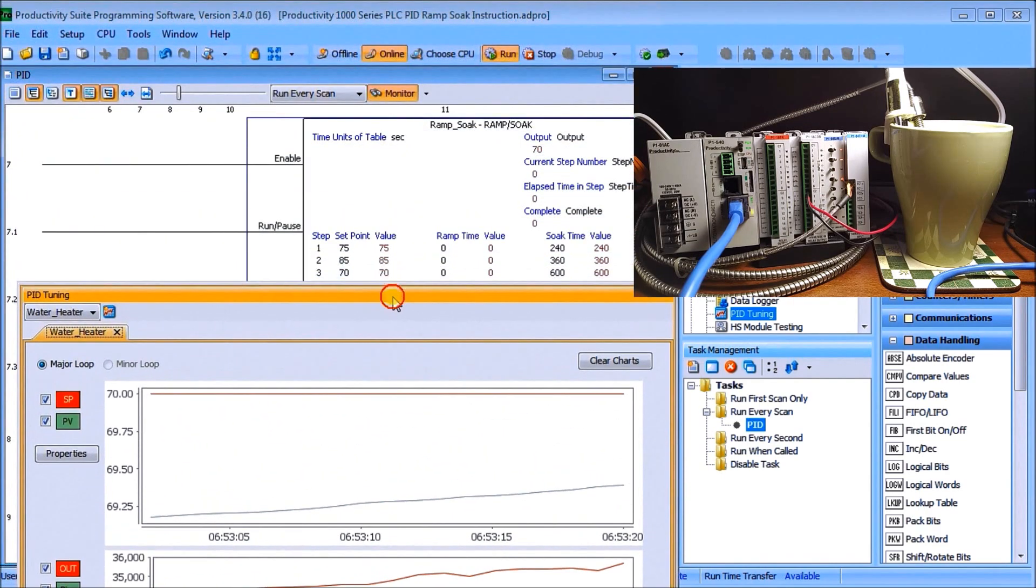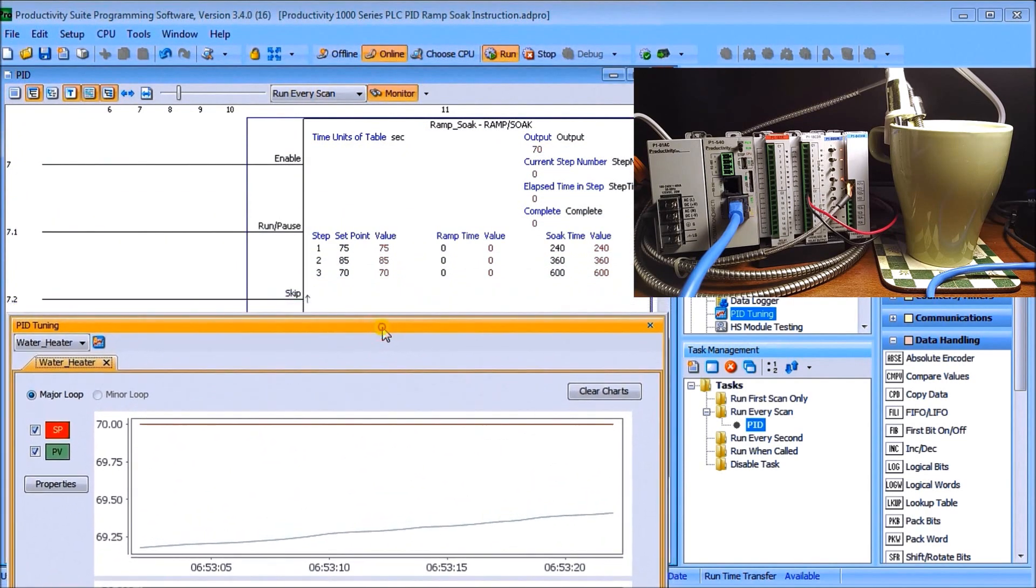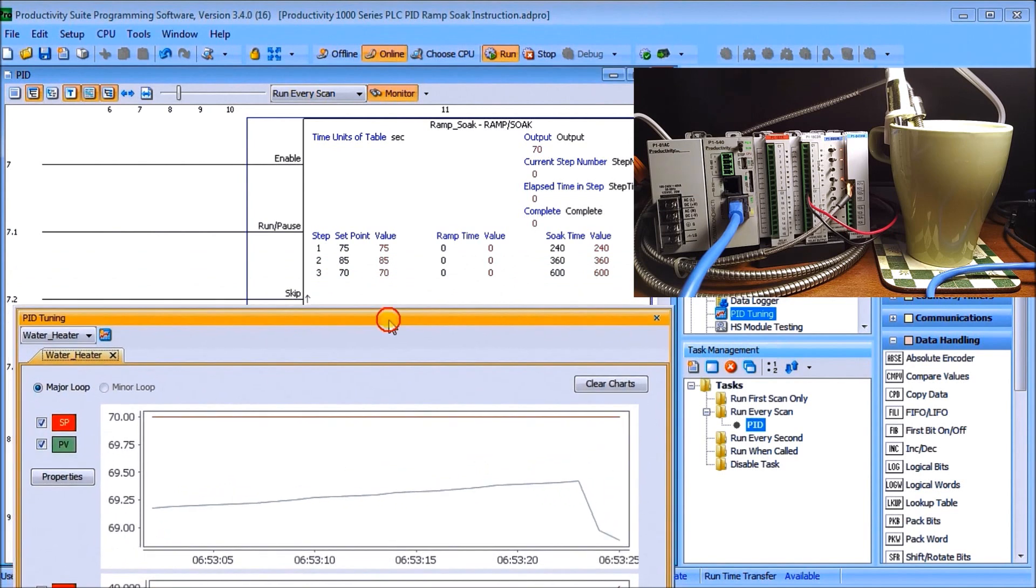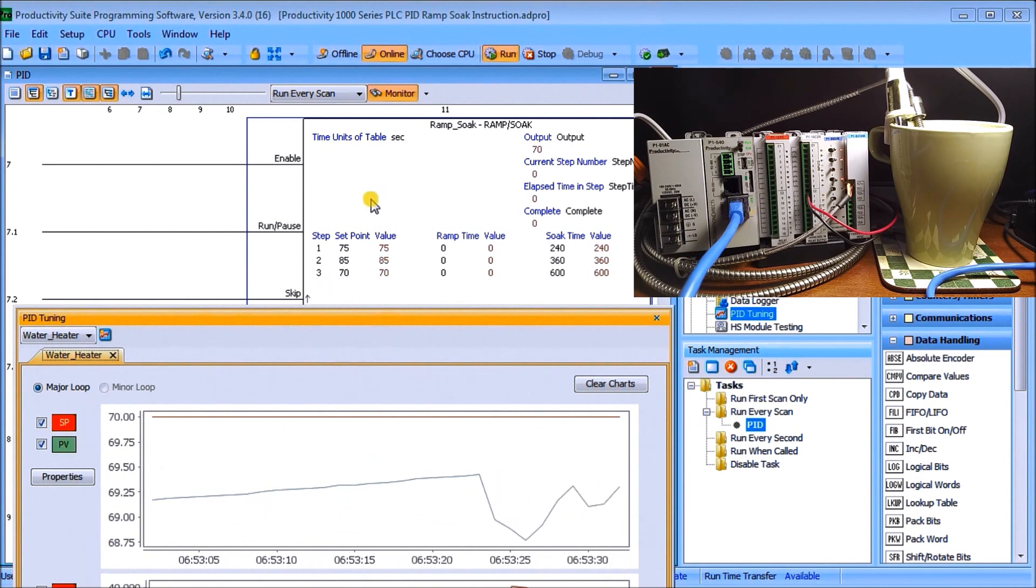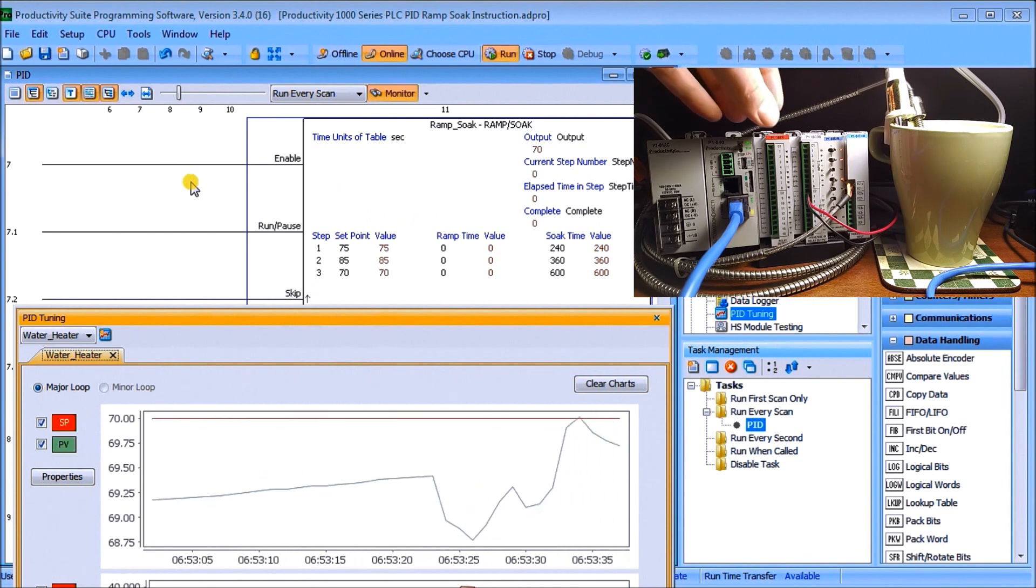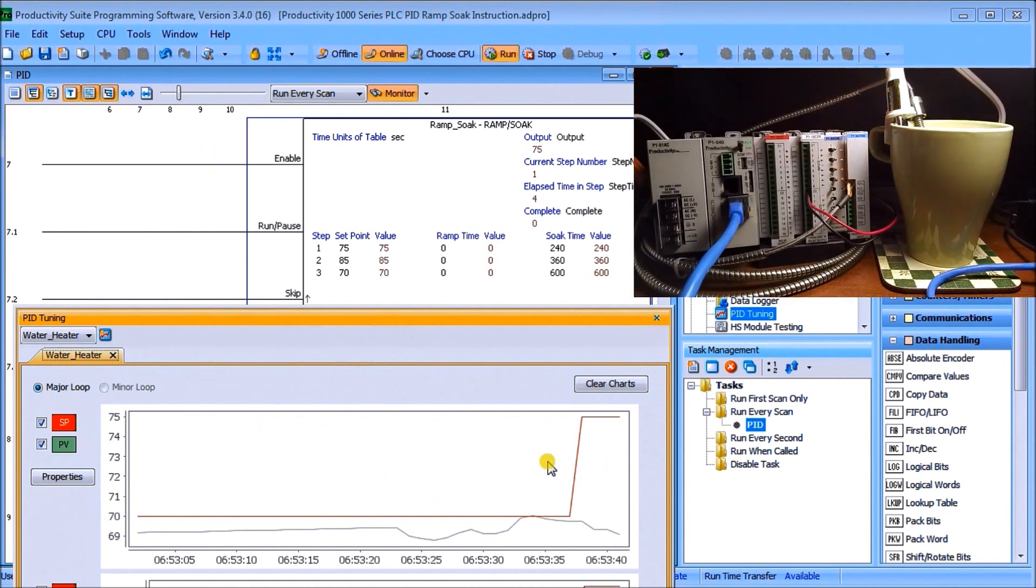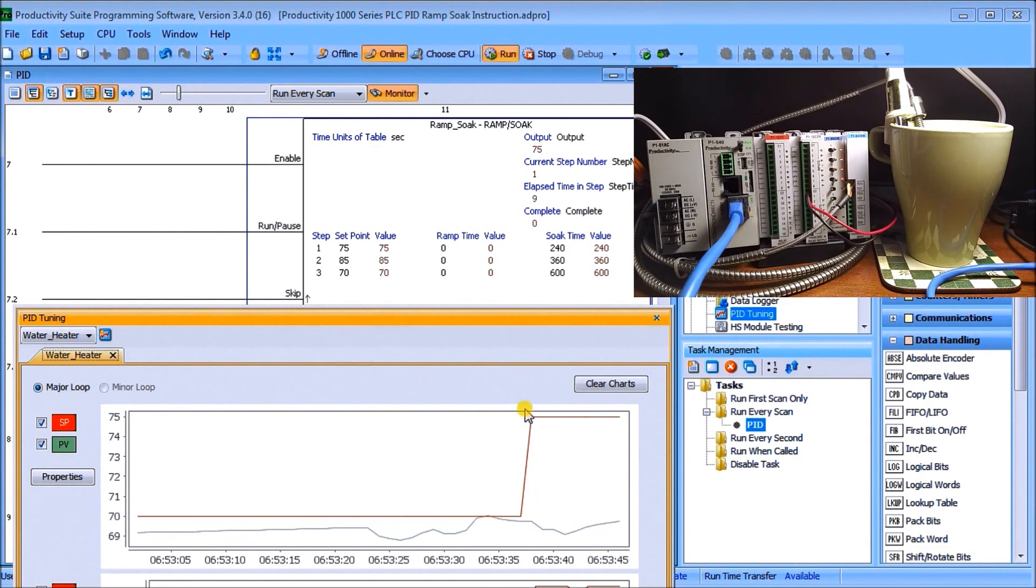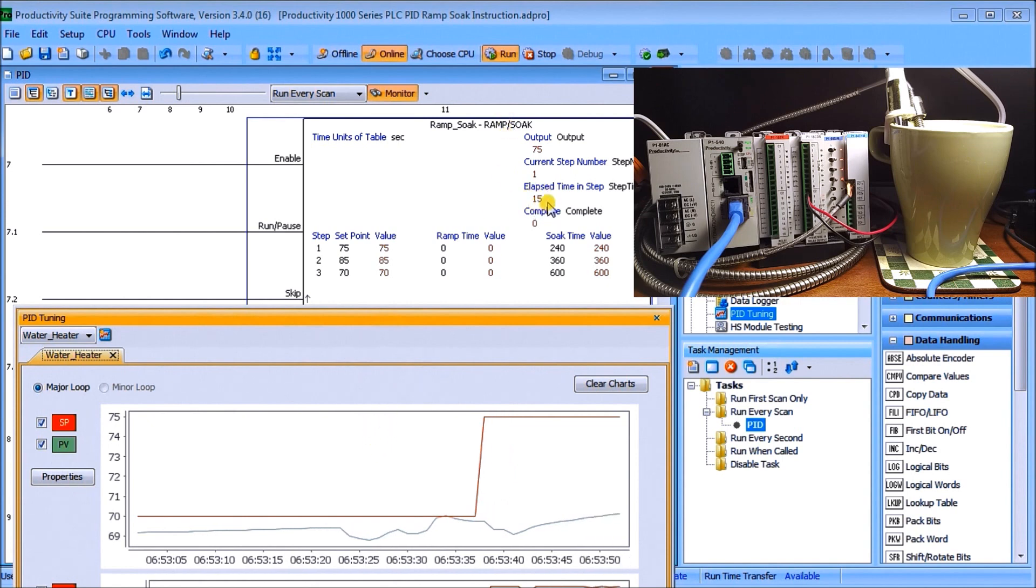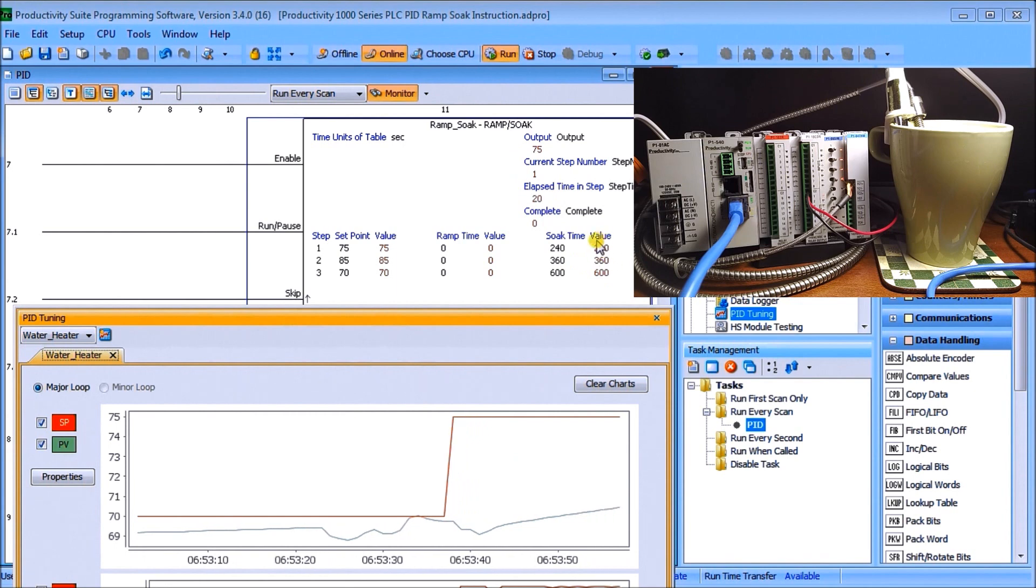So what we'll do is we'll just lower this down a little bit so we can see our information right here and then what we'll do is we will enable our ramp soak. So when we do that we'll turn on switch number three and when we do, what you'll notice is that our set point now goes up to 75 and our output is now climbing and you'll see my elapsed time now we will go up to 240 seconds.